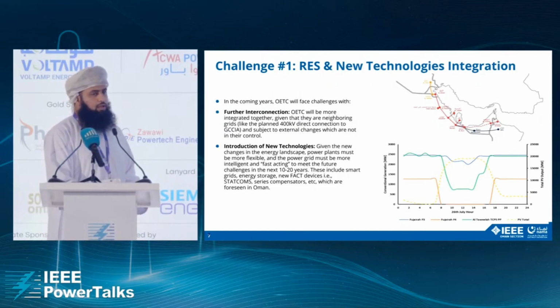So now I will go through the main challenges that will happen if we have high penetration of renewable energy. Oman has interconnected with GCCIA through a 220 kV system from UAE, and it will be upgraded to 400 kV. This integration, due to all the Gulf targeting to have renewable energy in their system, and a high impedance of interconnection between Oman and the other GCCIA members, will introduce an oscillation, an intermediate oscillation, that needs to be captured and needs a proper solution in order to damp that oscillation.